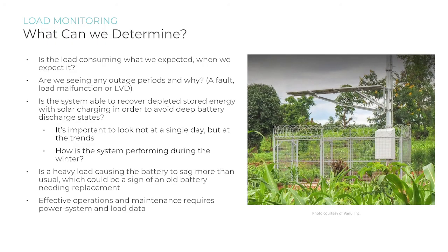For example, batteries are a major cost component of the system, and depending on size, you can get fairly specific data indicating a battery failure. We had a recent site with extensive data logging where multiple data points clearly pointed to current being consumed in almost a short-circuit scenario by the battery, an immediate voltage drop, no performance by the load, and a disconnect that threw off some faults. They knew immediately a battery replacement was needed without even visiting the site. It was a single field replacement, and it was warranted because that kind of clear data can't be argued with.